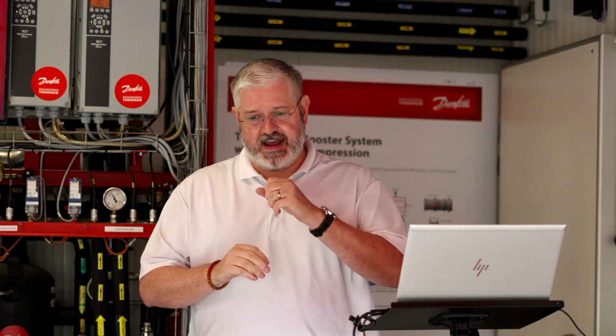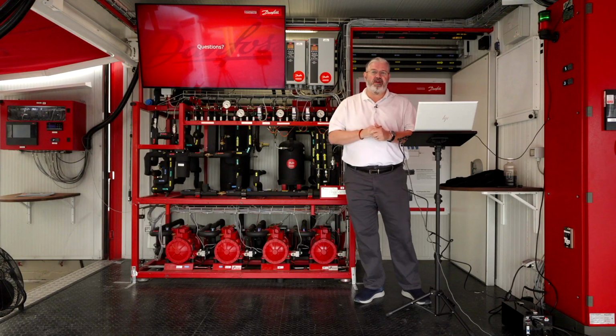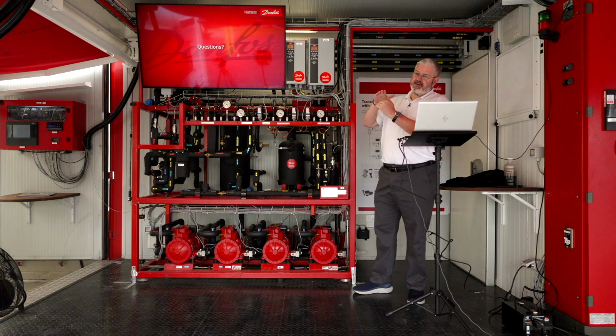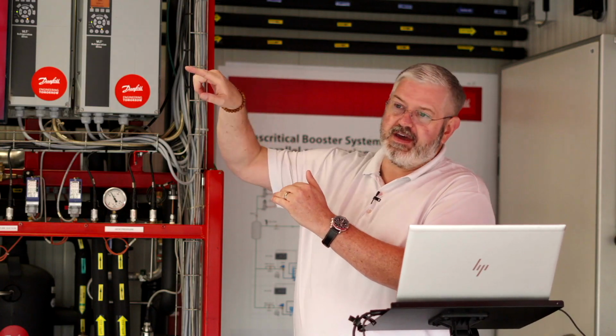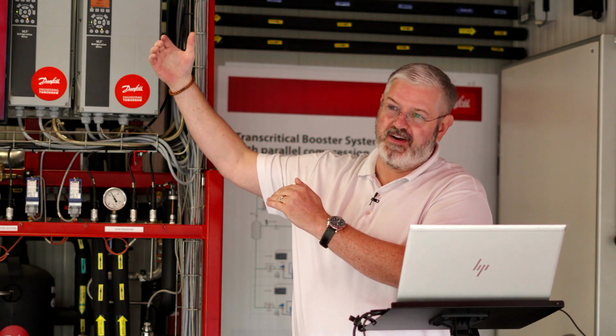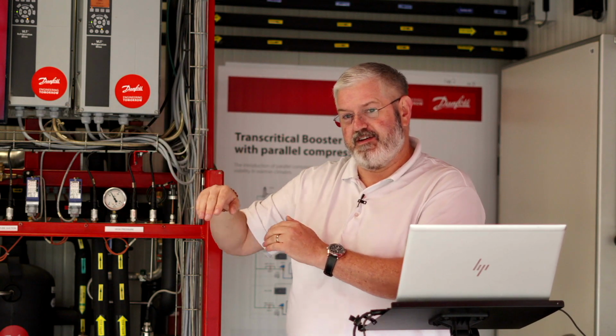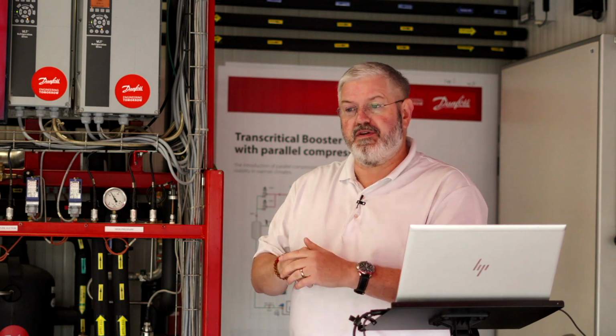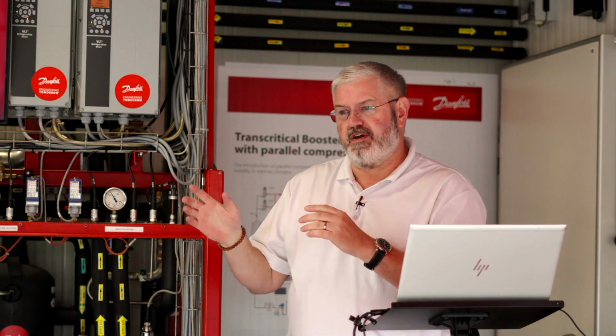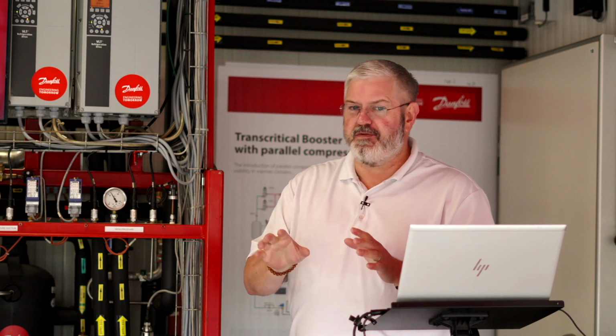with it, but you can just kind of think of it, as think of it similar to like a heat reclaim valve feeding a hot gas line. You're going to go reverse piping through the evaporator around a check valve. It's very similar to the hot gas defrost you would see on an HFC, but again, at higher pressures. So you have to temper that pressure before you send it to the evaporator, because the high side of the system, from the discharge of the compressor all the way back around to the high pressure valve, that's rated at 159 bar. The evaporators on the other side of that, they're at 59 bar. So there are some components necessary between the discharge heat that's available and what you send to the evaporator. It's a little complex, but very doable.